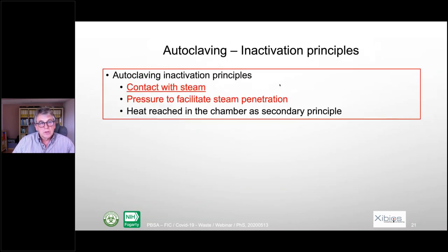One thing which is very important to know and understand is that the principle of bacterial or viral inactivation when autoclaving is really the contact with steam. So it's not just heat, we need the contact between the steam and the microorganism. And actually we use the pressure to be able to work at a temperature higher than 100 degrees, but also to facilitate steam penetration inside of the waste bags, for instance, inside of the microorganism. And so the heat itself is a secondary principle, but the main active principle, I would say, is the contact with steam.